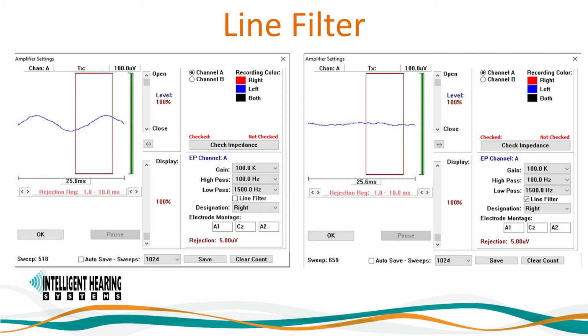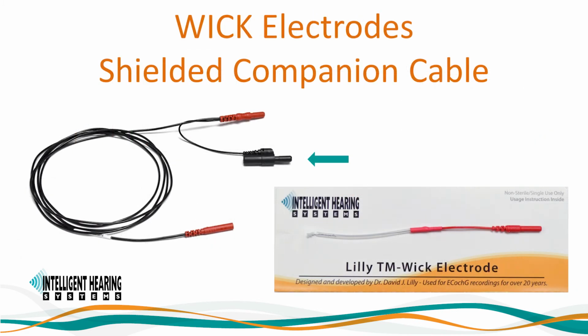If interference is clearly 60 or 50 Hz mains, and all efforts have failed, including obtaining approximately equal and low electrode impedance to reduce it to a workable level, then the use of a notch line filter may allow testing to continue. You can turn on the line filter from the EEG and amplifier screen for each channel. Now let's move on to the electrodes and how these choices can affect your recordings. For example, in ECochG, Intelligent Hearing Systems manufactures the Lilly TM-Wick electrodes.